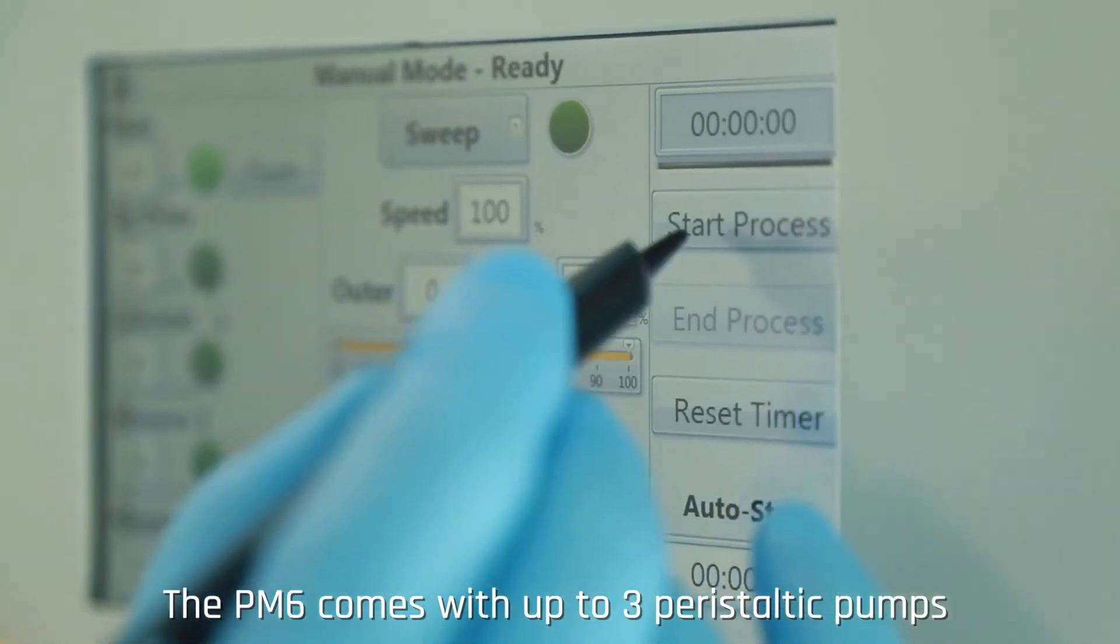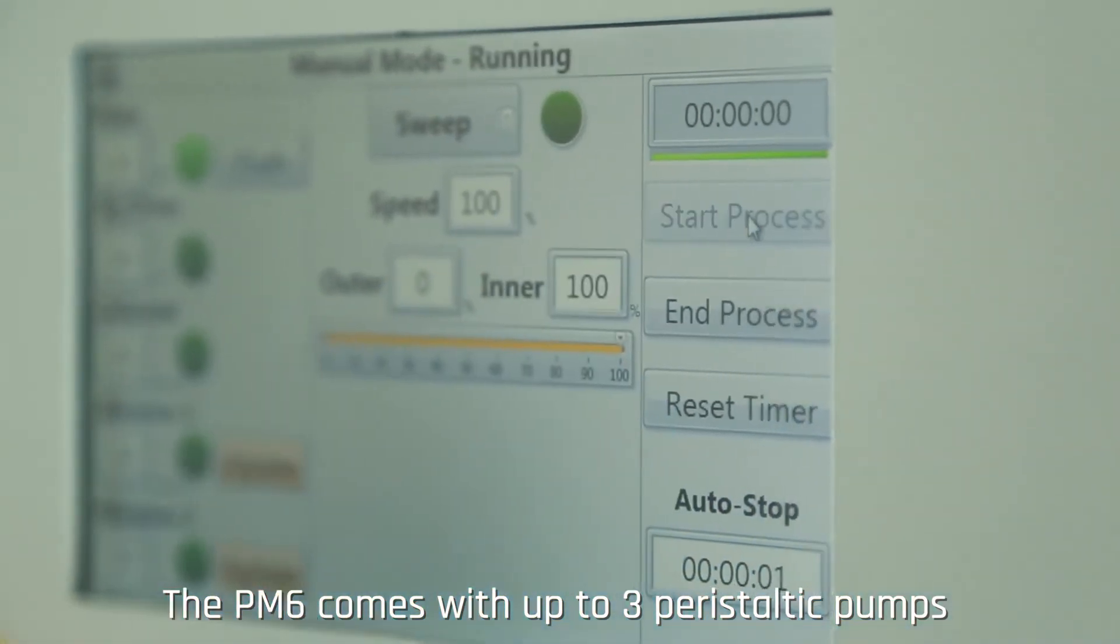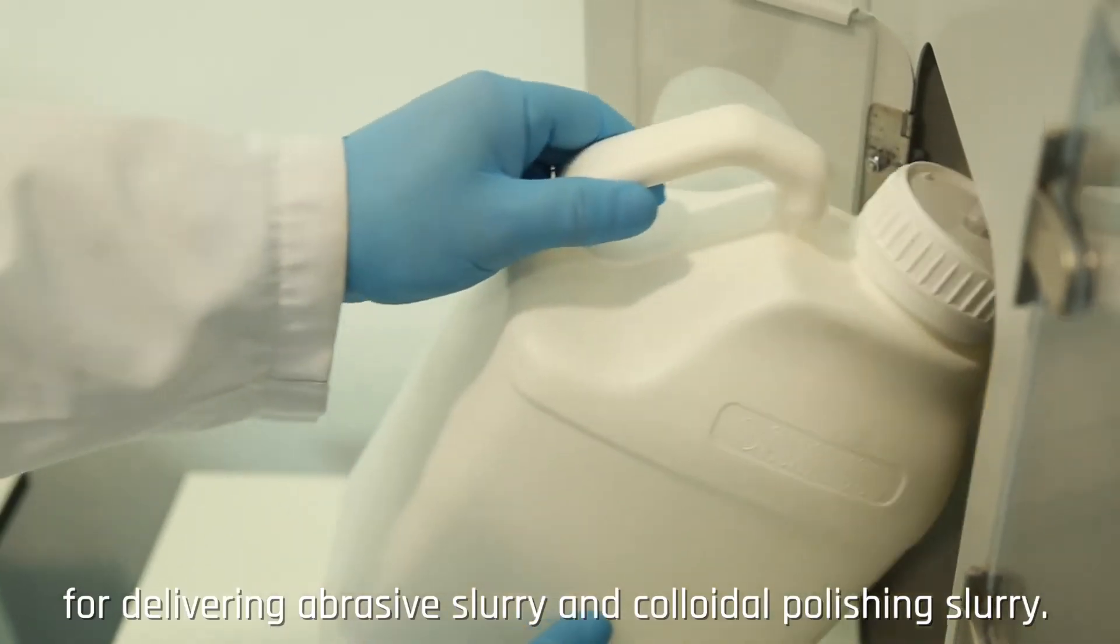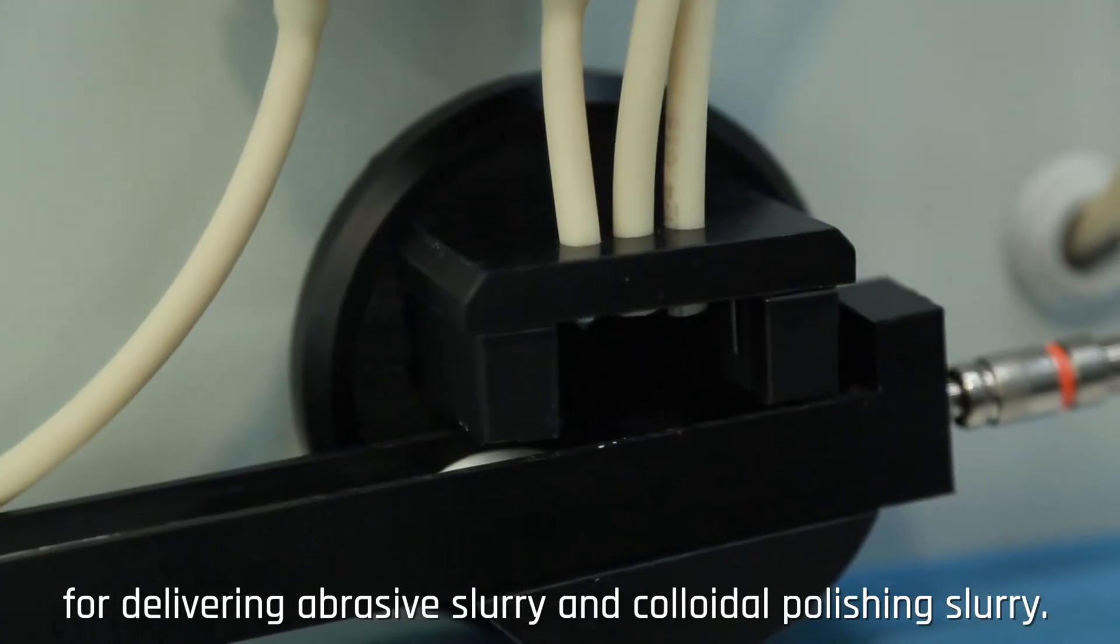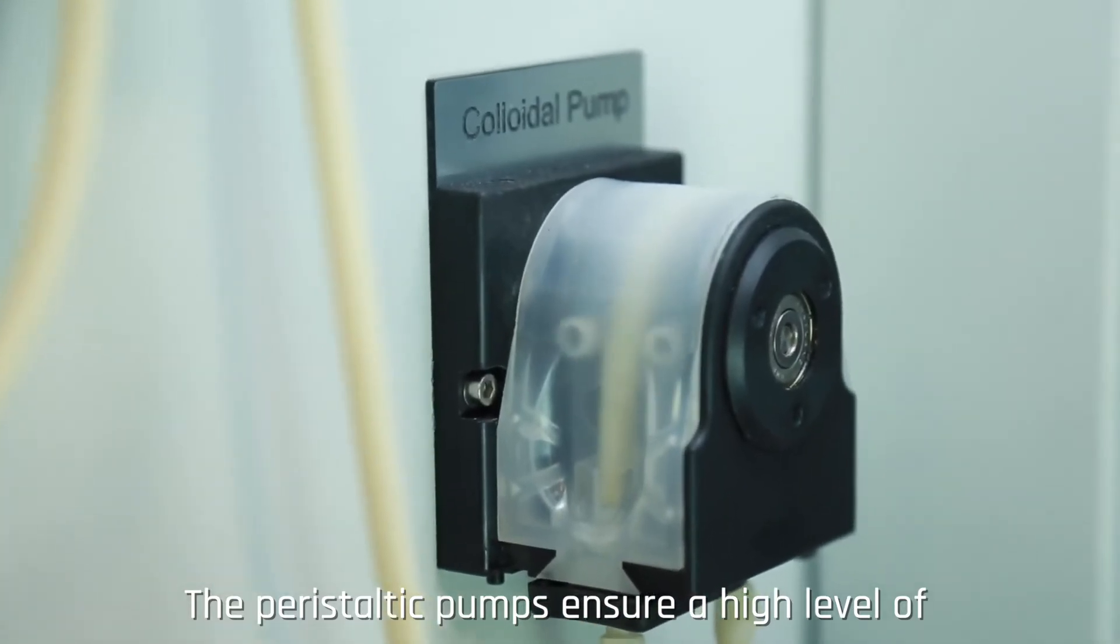The PM6 comes with up to three peristaltic pumps for delivering abrasive slurry and colloidal polishing slurry. The peristaltic pumps ensure a high level of process control and repeatability.